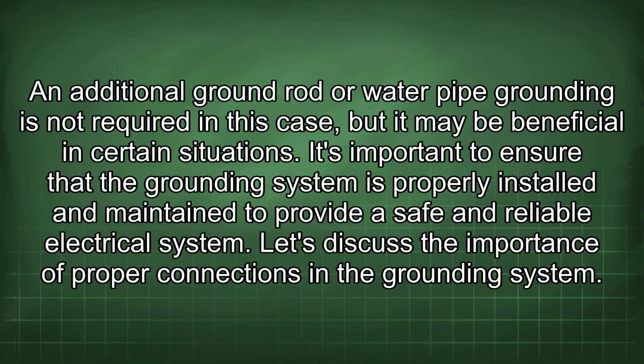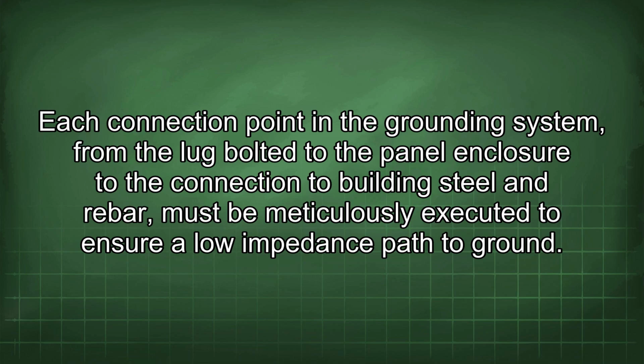It's important to ensure that the grounding system is properly installed and maintained to provide a safe and reliable electrical system. Let's discuss the importance of proper connections in the grounding system. Each connection point in the grounding system, from the lug bolted to the panel enclosure to the connection to building steel and rebar, must be meticulously executed to ensure a low impedance path to ground.